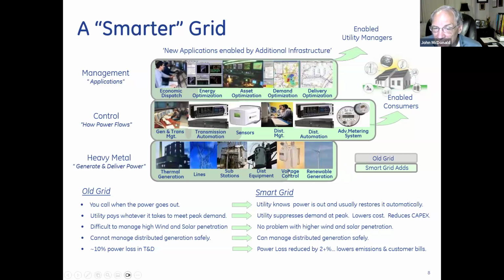For instance, on voltage control, I've shaded it halfway. Voltage is directly proportional to load, so if I want to manage load, I lower the secondary voltage to lower the load. We've been doing voltage control and reactive power control separately for many years; today we integrate those two together. We call it integrated volt-var control, and that's the green part of this.